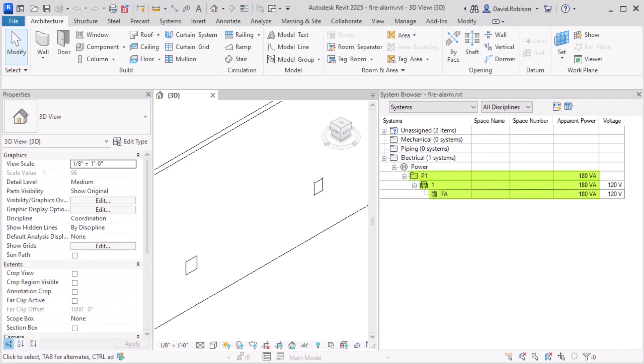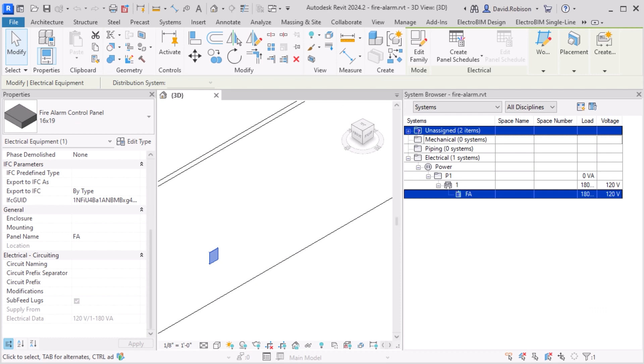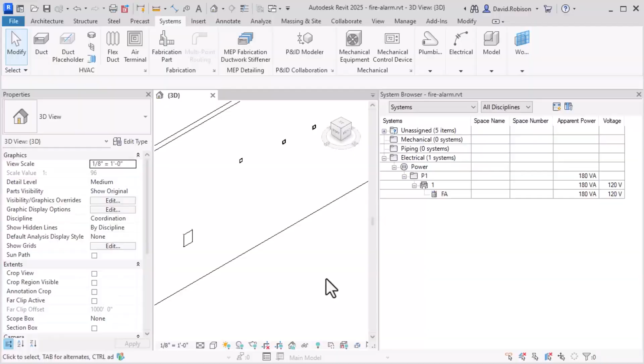The final electrical feature is the maximum number of circuits on low voltage panels. This is a new parameter on electrical equipment categorized as other panels. If we go back to Revit 2024 and look at that fire alarm panel, under the circuiting category there's nothing related to number of circuits. We can load up as many circuits on this fire alarm panel as we want, and it won't warn us or prevent us from doing anything.